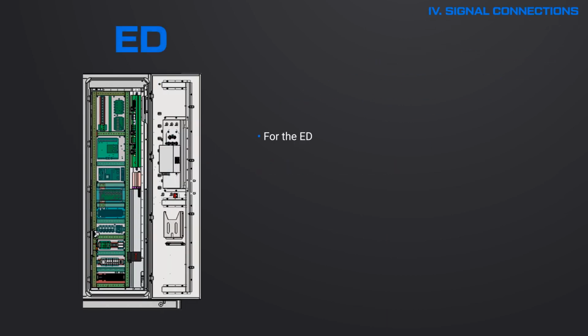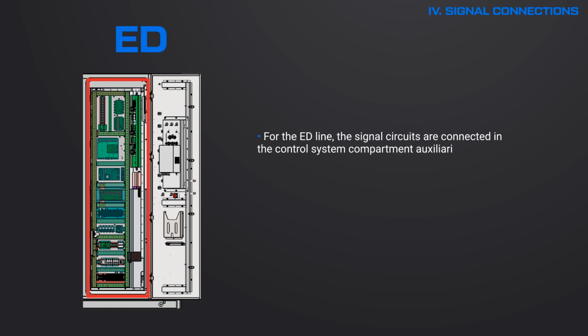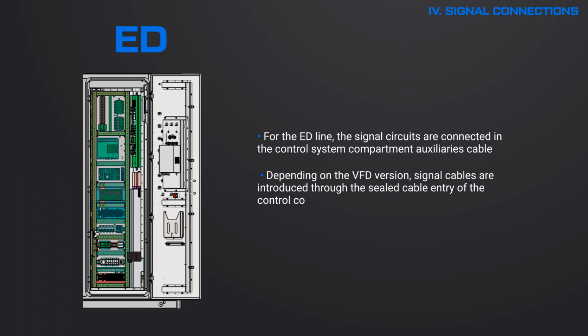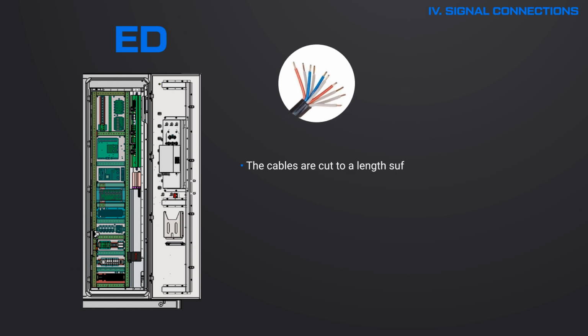Signal connections. For the ED line, the signal circuits are connected in the control system compartment auxiliaries cable. Depending on the VFD version, signal cables are introduced through the sealed cable entry of the control compartment, located in the lower part of the compartment. The cables are cut to a length sufficient to allow restripping and connection.